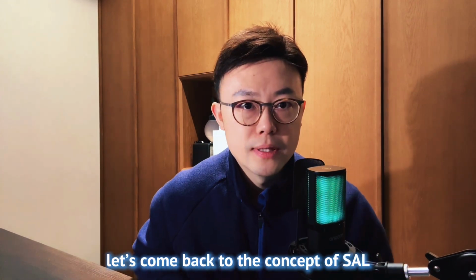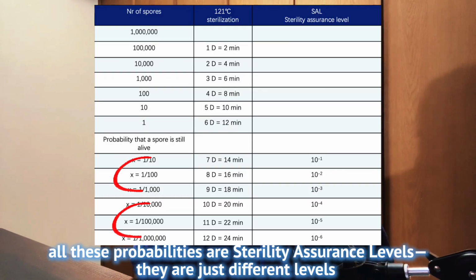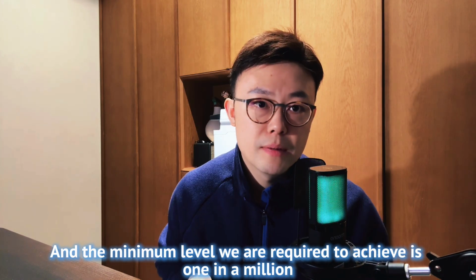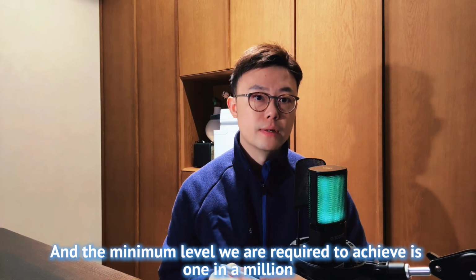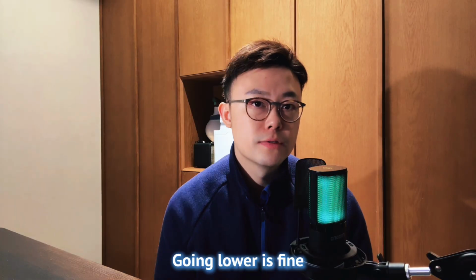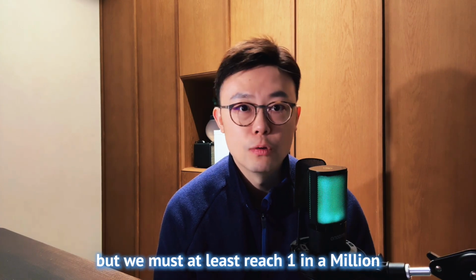Now let's come back to the concept of SAL. All these probabilities are sterility assurance levels. They're just different levels, and the minimum level we are required to achieve is 1 in a million. Going lower is always fine, but we must at least reach 1 in a million.